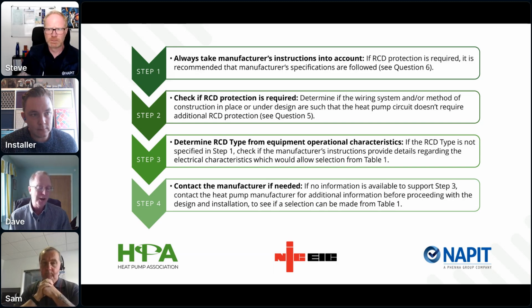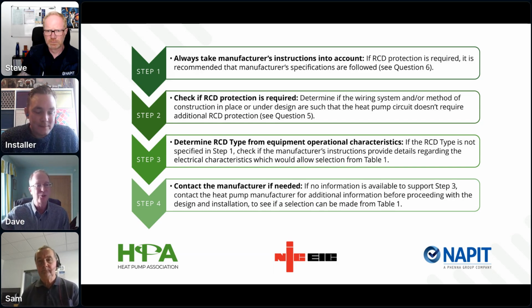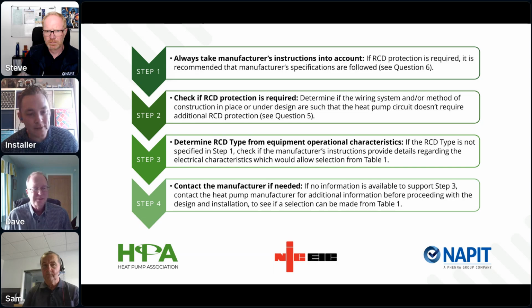And of course, just to go back to the point we made earlier, manufacturers' instructions often say things very differently from one to another. One manufacturer may just say do X. Another manufacturer might say, well, do X if an RCD is required, leaving the door open to the circumstances we've just been talking about where it might not be required. In which case you are following the manufacturer's instructions. Yeah, you can see why you have made this guidance, to help with these potential grey areas. So on there, we've got steps 3 and 4, which cover selecting the RCD type from the manufacturer's instructions or information obtained by contacting the manufacturer.